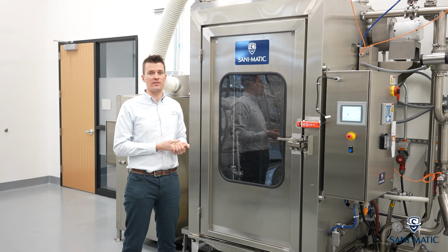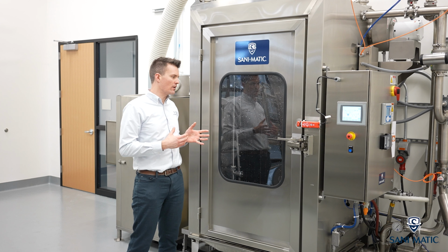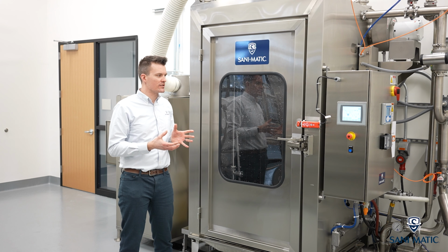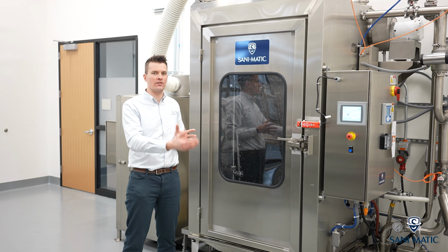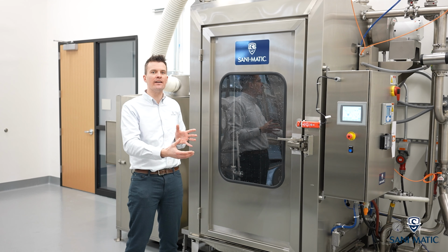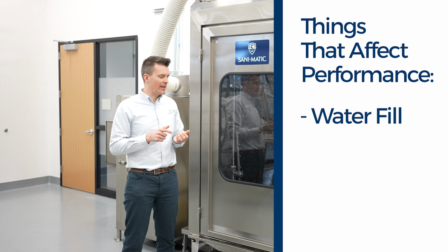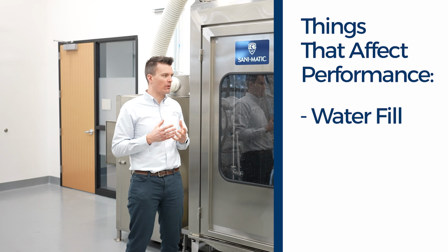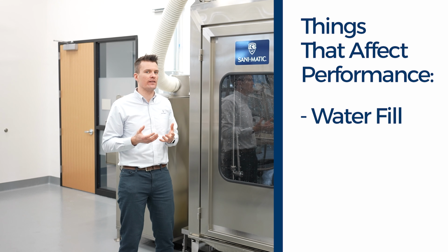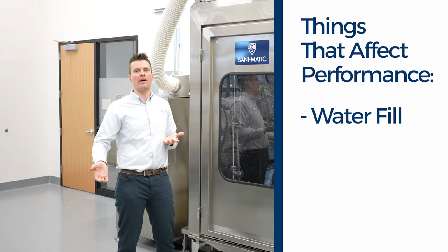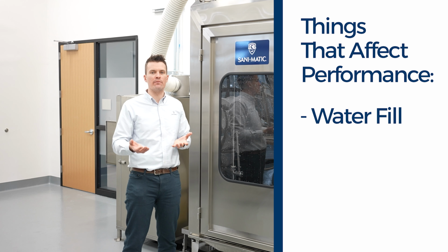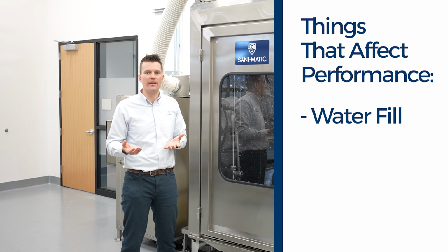By contrast, the impacts on performance are basically things that slow down the cleaning cycle speed. So I want to wash, whether it's a CIP or a cabinet washer, as fast as I can. Things that slow this process down are a couple of things. One, utilities like water fill. So if I have lower pressure and my water is filling slower today than it was yesterday, that's going to extend my cycle time and degrade my performance score.